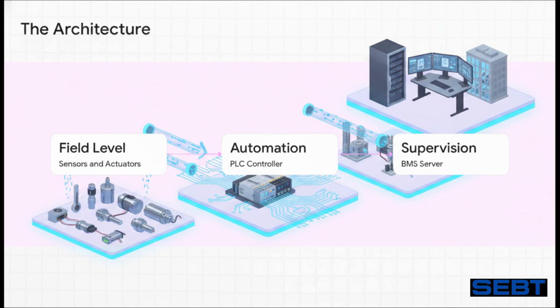So our entire architecture flows sequentially through three very distinct layers. First up, right at the bottom, we've got the field level. This is physical reality, okay? The actual sensors gathering data and the actuators ready to make a move. Second, we step up to the automation level. This is our PLC. It's the machine brain taking all that raw data and making split-second logical decisions. And finally, we ascend to the supervision level. This is the BMS server and the operator workstation. It's where facility managers actually sit down to monitor trends, tweak schedules, and optimize the whole building as one massive holistic system.